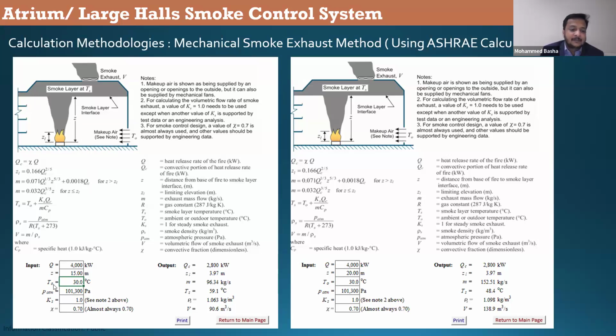And the makeup air temperature, TO, you are providing from here, which is 30 degrees, I'm assuming. You can change this value as you require. Treated fresh air, some people will be using, or direct, untreated fresh air, depending on the temperature. You can change the outside air. It has a small impact on the smoke exhaust volume, not a huge one, but a small impact. The amount of makeup air supplied is not mentioned here. It should be around 80 to 90%, as mentioned in NFPA 92.